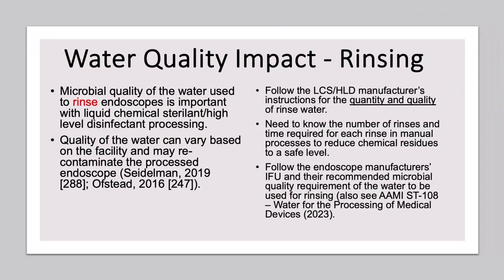Now, we talked about water quality. It's even more important in the rinsing. Microbial quality of water used to rinse endoscopes is very important, especially with liquid chemical sterilant and high-level disinfectant processing. The quality of the water can vary greatly based on your facility and can actually recontaminate the processed endoscope. So you must follow the liquid chemical sterilant high-level disinfectant manufacturer's instructions for the quantity and quality of rinse water. You also need to know the number of rinses and the time required for each rinse in manual processes to reduce the chemical residue to a safe level. Follow the endoscope manufacturer's instructions and their recommended microbial quality requirement of the water to be used for rinsing. And again, you will find some recommendations in ST108.